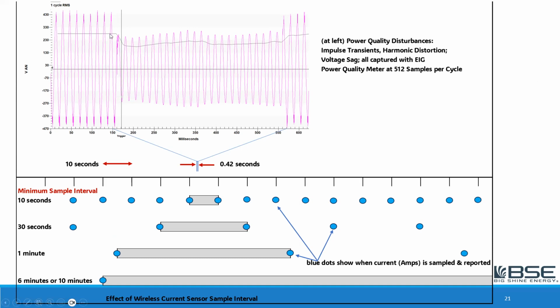Something started up in the building. Maybe it was this device that this phase was connected to, and it pulled down the voltage for a few cycles, and then the voltage rebounded. And for a moment there were some irregularities and a little bit of harmonic distortion. But this whole event took place in about 0.42 seconds, less than half a second. So it means that with these wireless current sensors, you're never going to see things like this. You won't have any idea that they're happening.